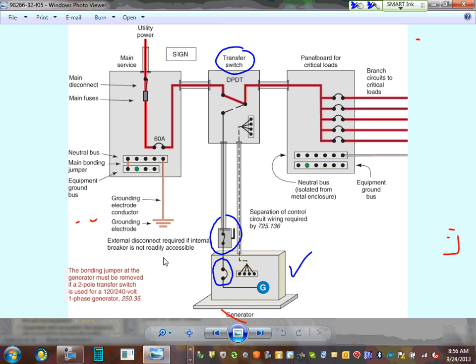Completely wired. I want to bring your attention, guys, to the control circuit. This is for control conduit. This is for power, going to a transfer switch. There are three types of transfer switches, guys. They have a manual transfer switch, where someone finishes their coffee, then goes and flips the switch. That's manual. There's an auto transfer switch.